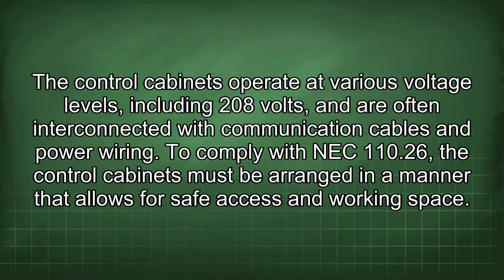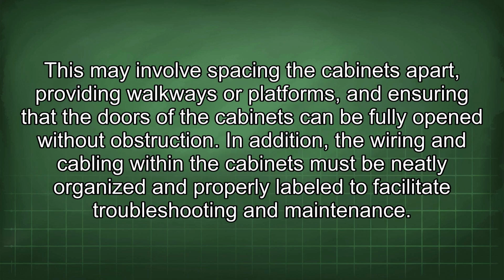110.26, the control cabinets must be arranged in a manner that allows for safe access and working space. This may involve spacing the cabinets apart, providing walkways or platforms, and ensuring that the doors of the cabinets can be fully opened without obstruction. In addition, the wiring and cabling within the cabinets must be neatly organized and properly labeled to facilitate troubleshooting and maintenance.